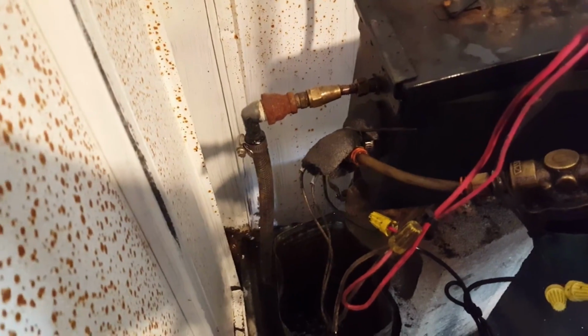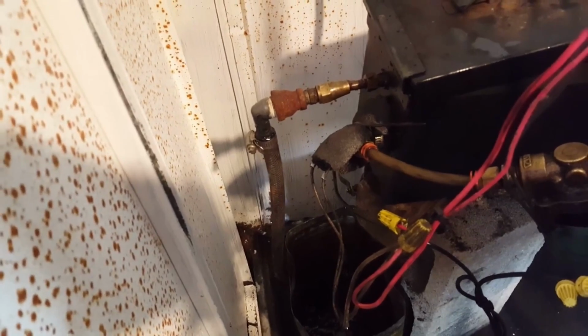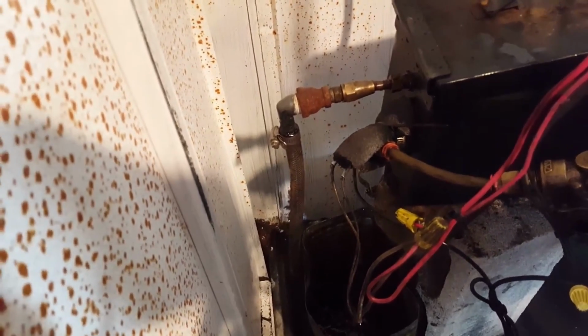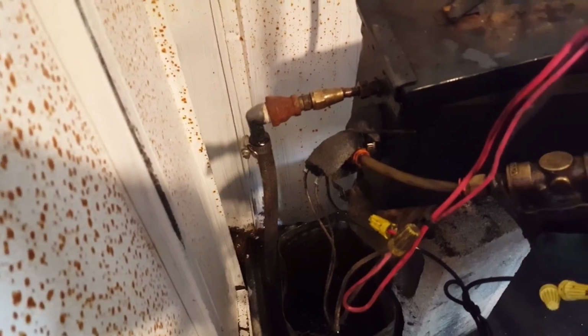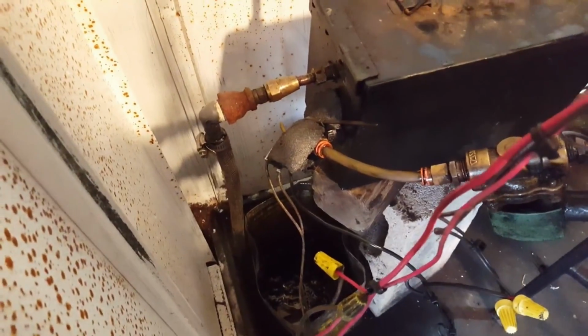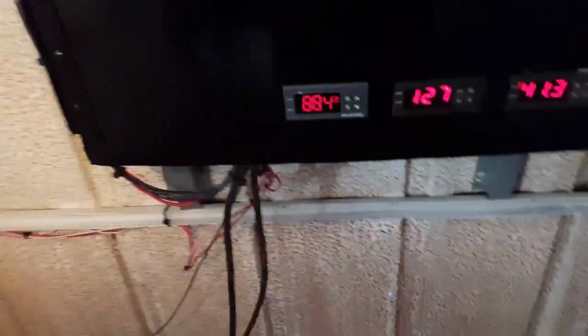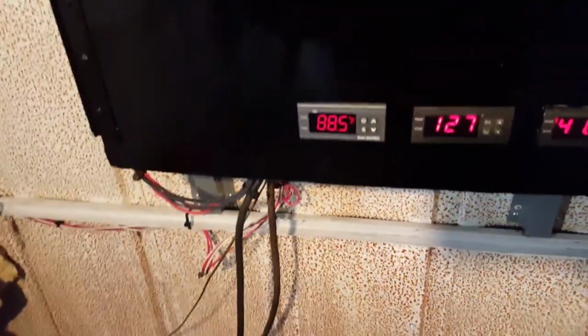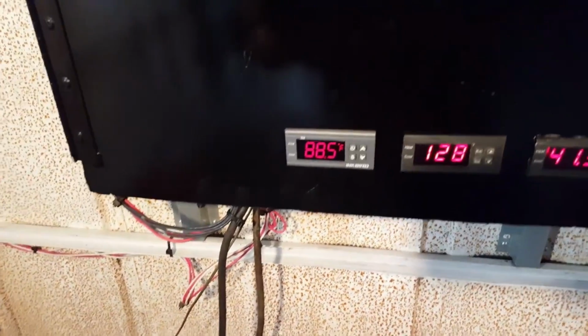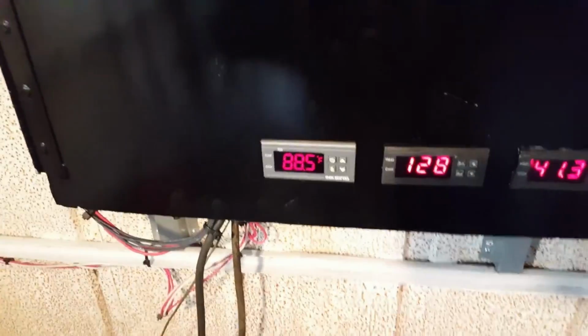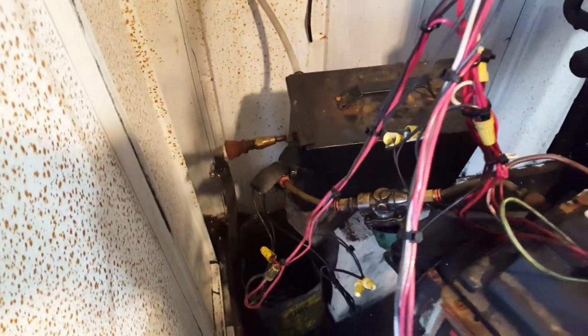So I've got to find a temperature sensor that'll work with that controller that I can stick inside there and measure the oil temperature. And because of that temperature sensor being where it's at, I want that oil at about 120 degrees, but I've got this temperature controller set at about 80 because it's not reading the actual temperature of the oil, and that's something I've got to get fixed pretty quick.